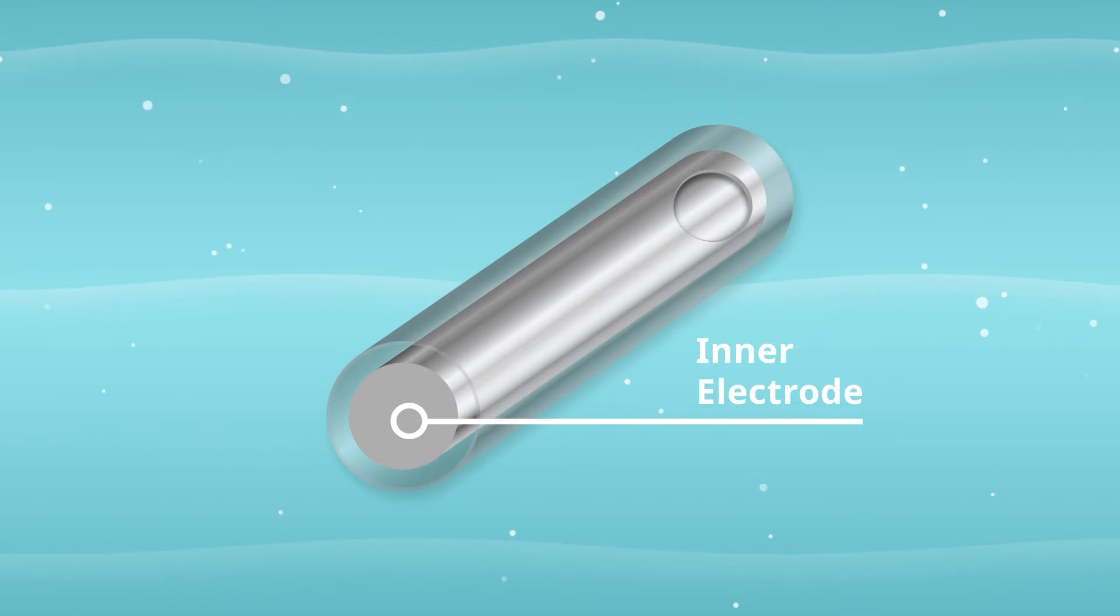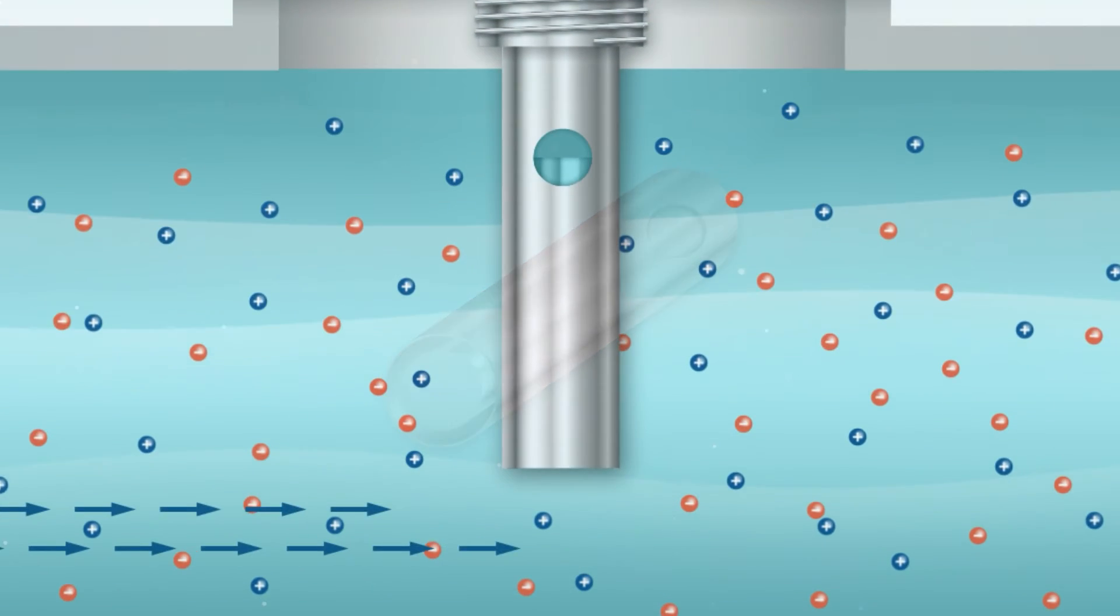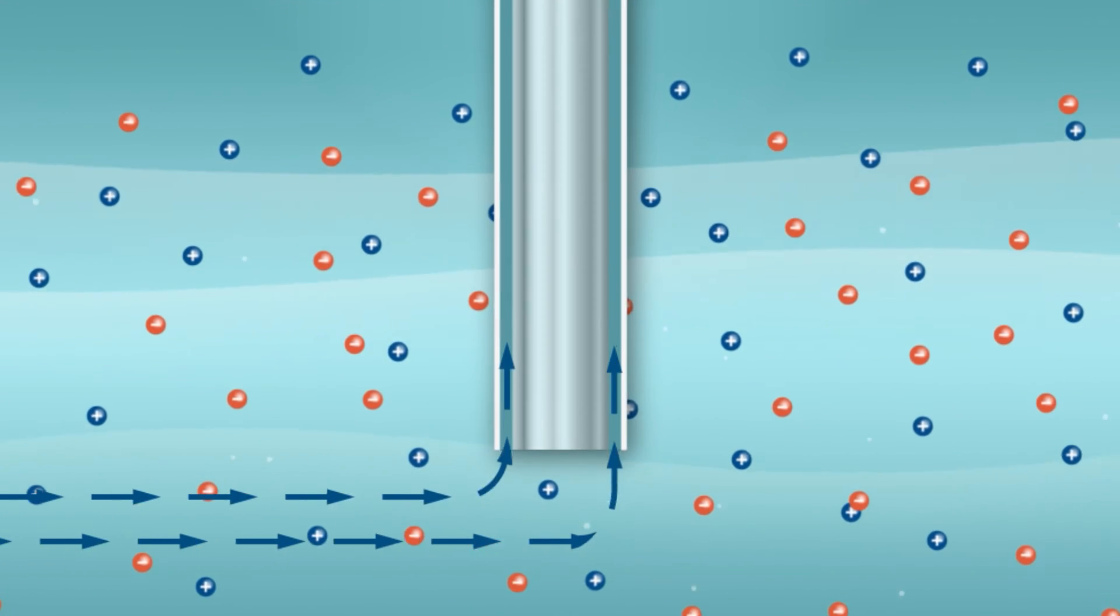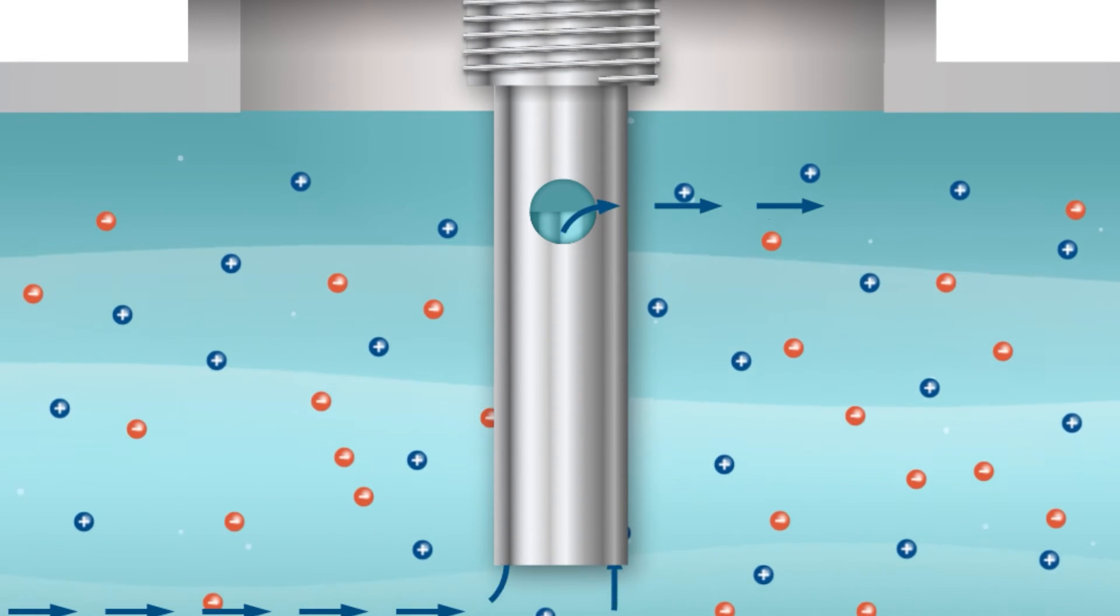The inner electrode region contains an RTD for automatic temperature compensation since fluctuations in temperature will impact conductivity readings. When immersed in process fluid, the fluid flows into the annular region between the inner and outer electrodes and then exits through the weep hole.